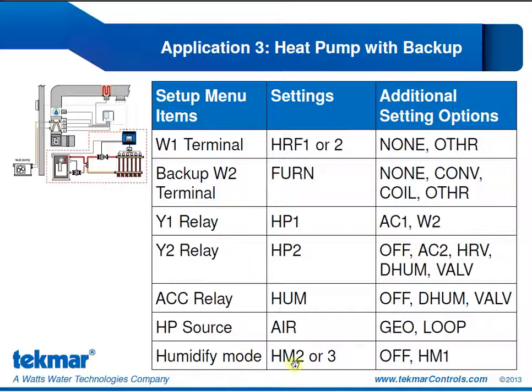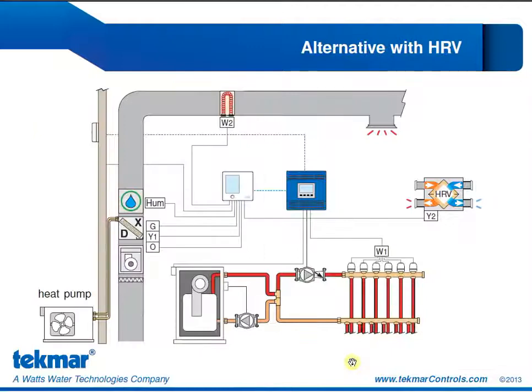Now we have to tell the 557 what the source is for our heat pump. In this case, it's an air source heat pump. And because that humidifier is in the ductwork, the humidify mode is 2 or 3.